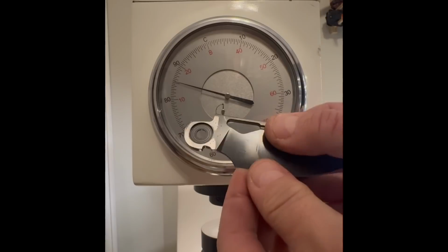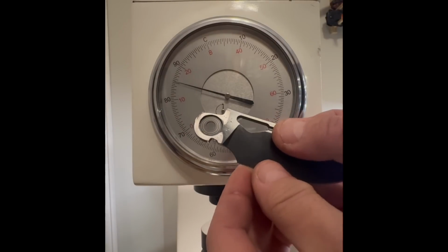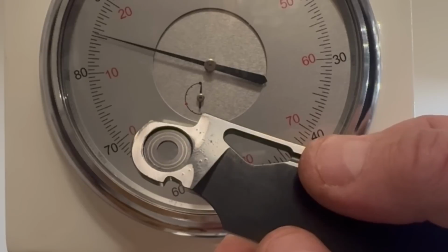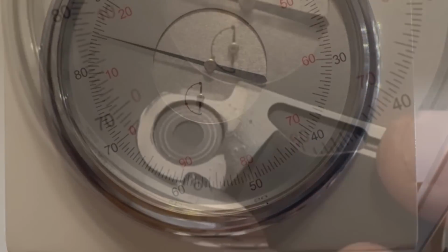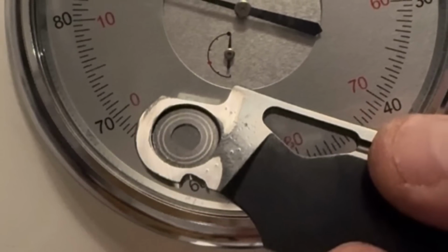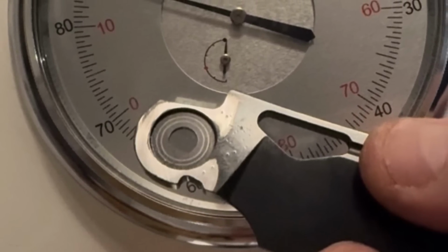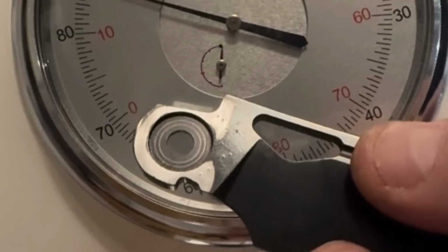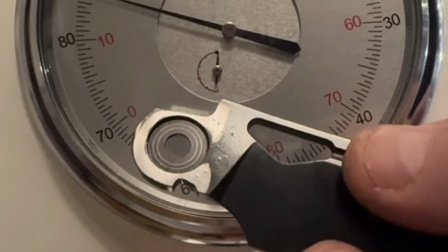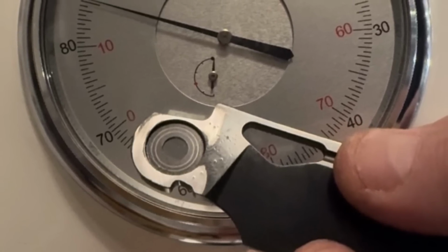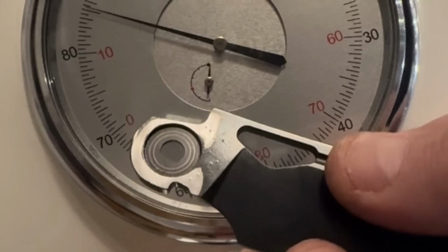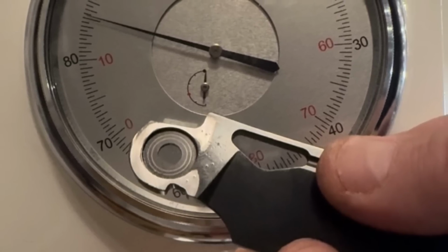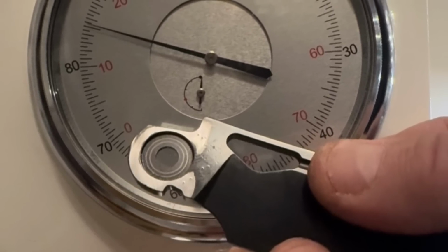And here are all the 6 pokes you can see on the blade, coated and uncoated parts. So let's go into averages. And the averages are 59.2 for the coated spots and 60 for uncoated. So indeed, the benchtop Rockwell tester is testing 0.8 point lower on the coated part of the blade.